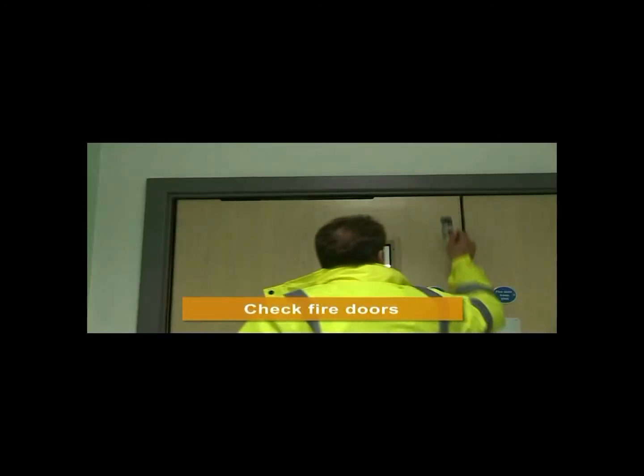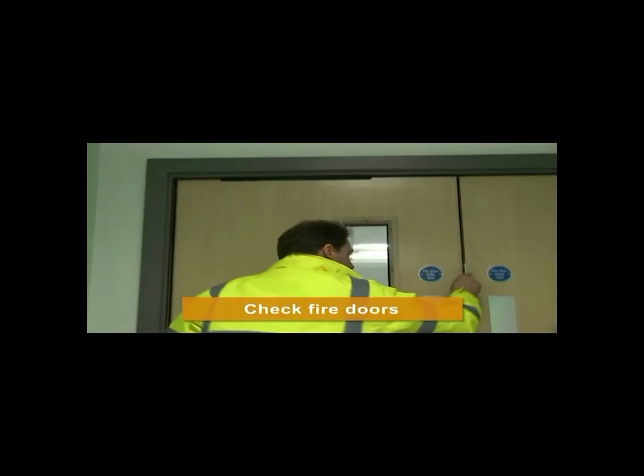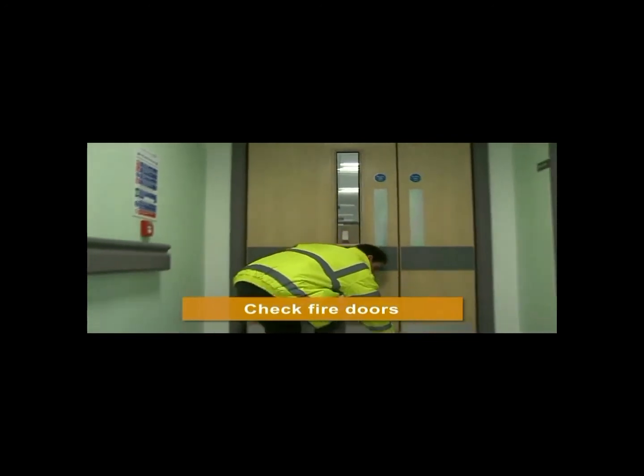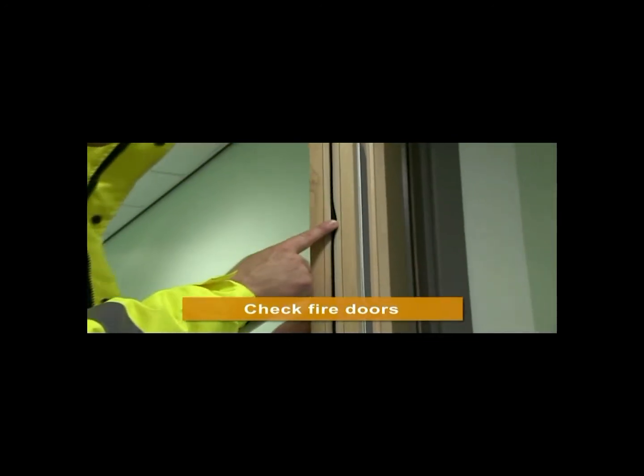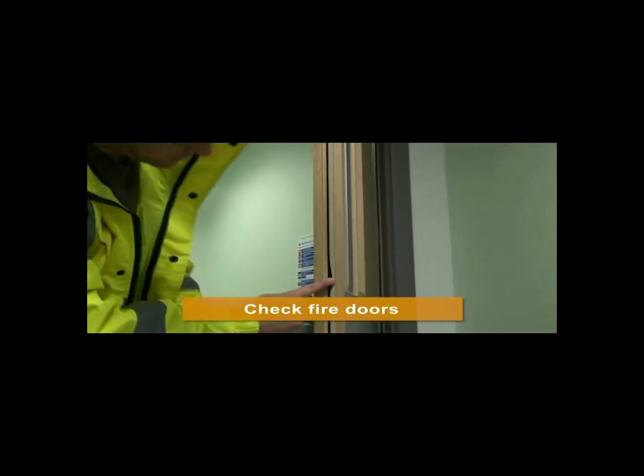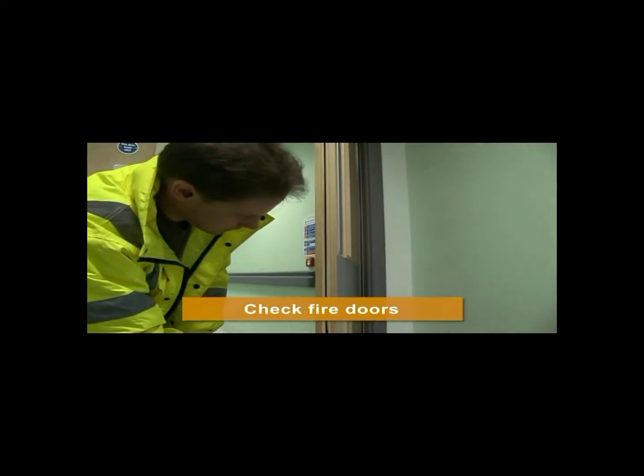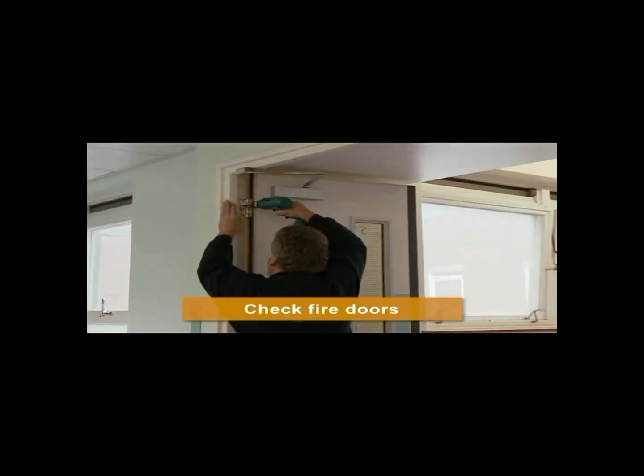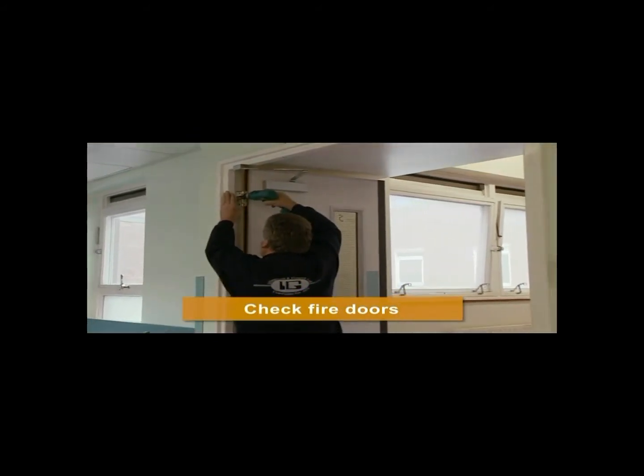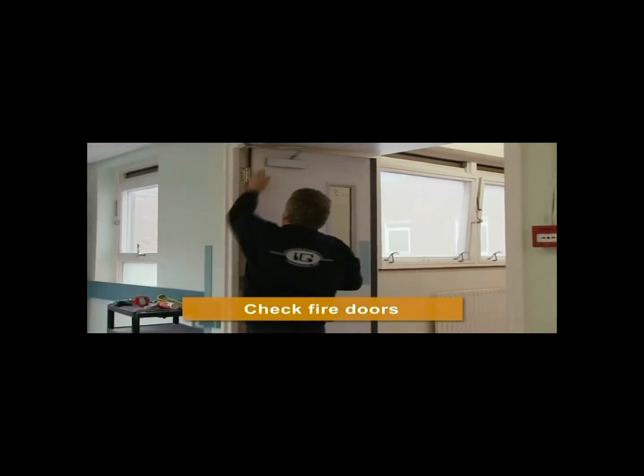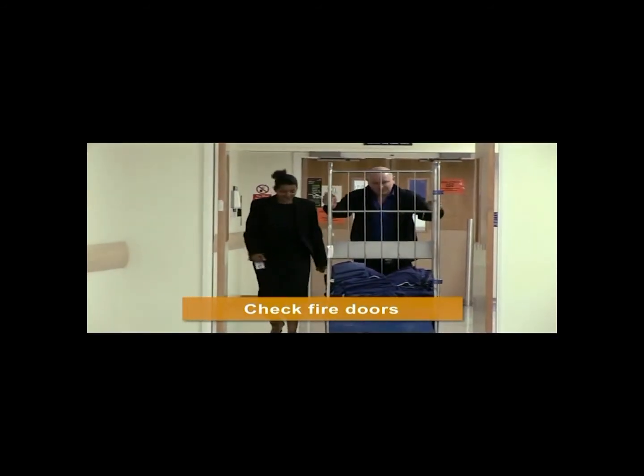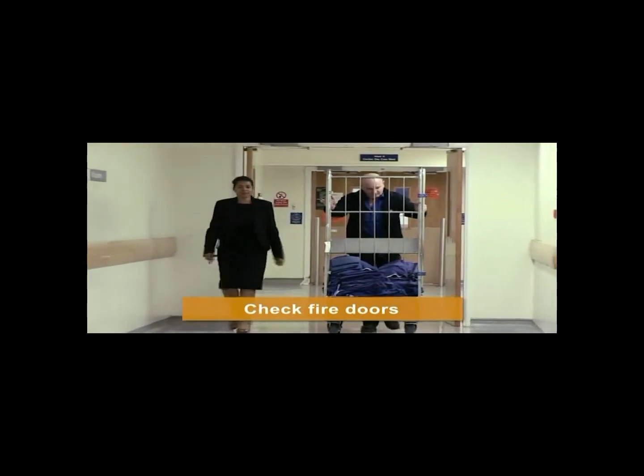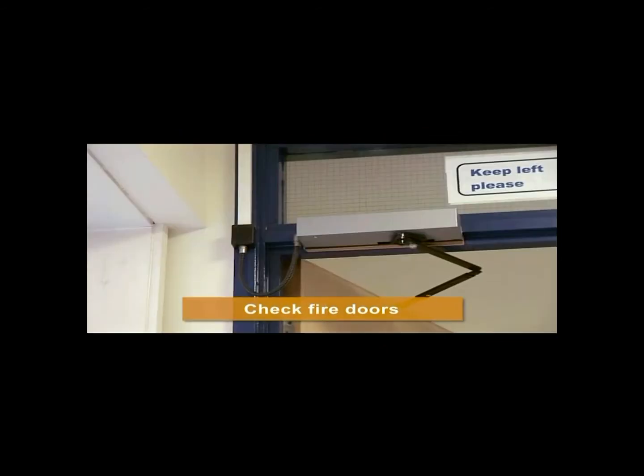Fire doors must be checked for correct fit and operation. Damage or poor maintenance can severely limit the time that a door will withstand fire, so they should be inspected regularly and any required remedial work should be carried out promptly. If fire doors do need to be held open, they should be fitted with hold-open devices that release and close the door when the fire alarm sounds.